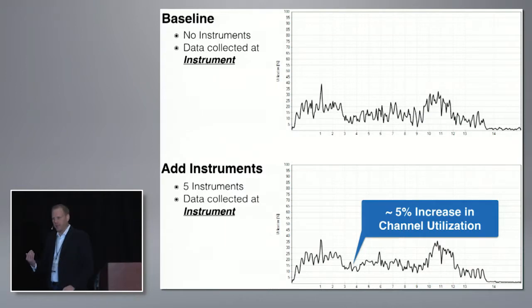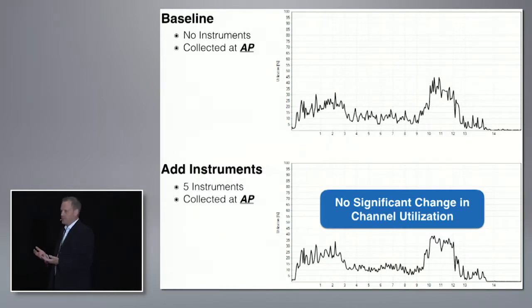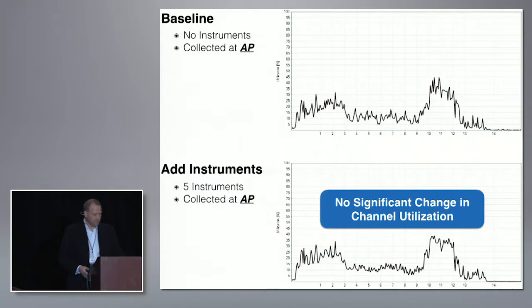This access point was approximately 20, 25 feet away from where the Wi-Fi client was. In a hospital, that's kind of typical; you're going to see the clients that far away. We looked at the spectrum analysis there, and there was really no change at all. Part of what we attributed that to is the fact that we implemented it as a Class 3 device. Right? So we're not blasting out the air and killing stuff. We're focused on the area within the patient's room for that communication.